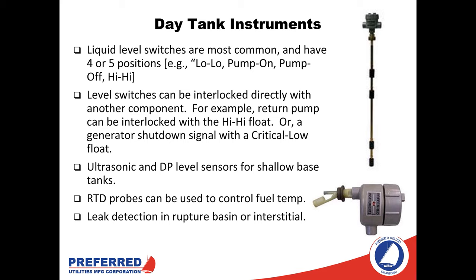Other devices on the day tank include leak detectors as well as RTD probes, as fuel temperature in the day tank is becoming more critical — both from generators returning hot fuel and in the northeast with fuel getting cold. Being able to tell the temperature at each part of the system can be important.